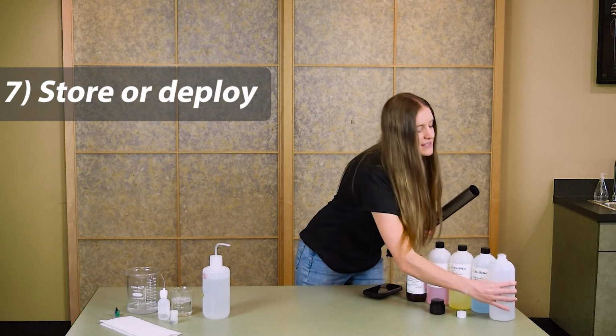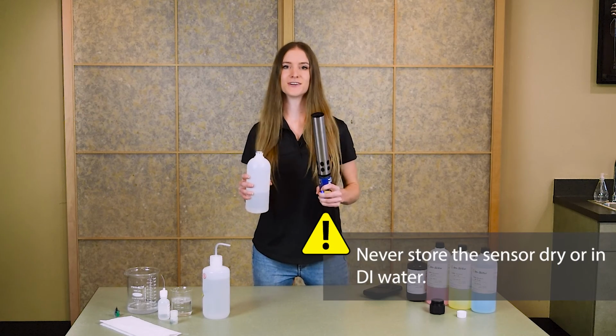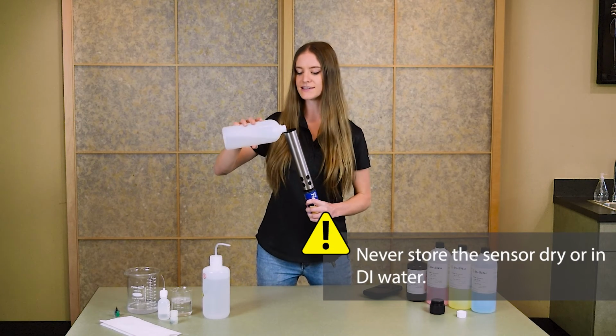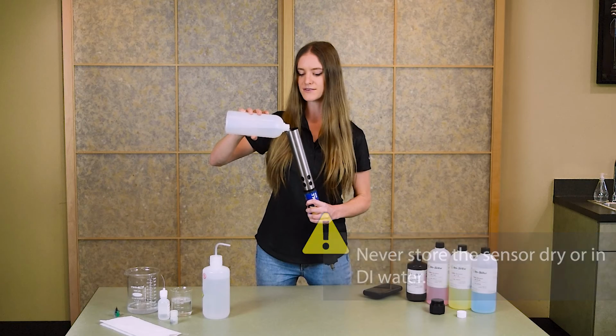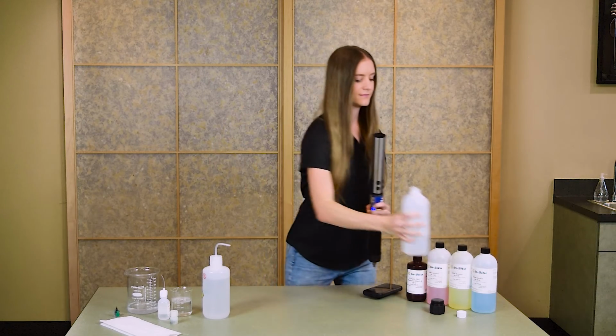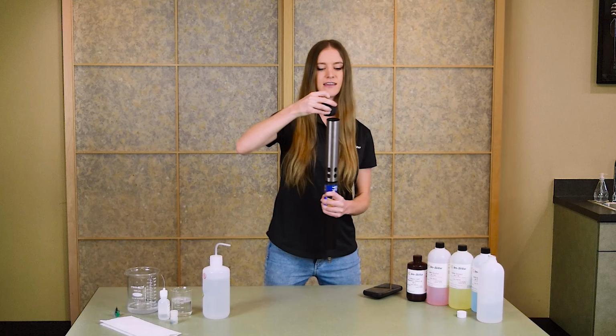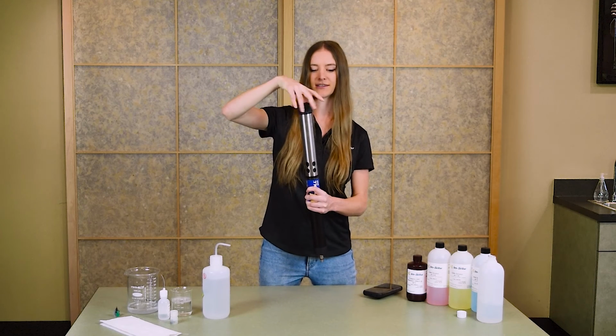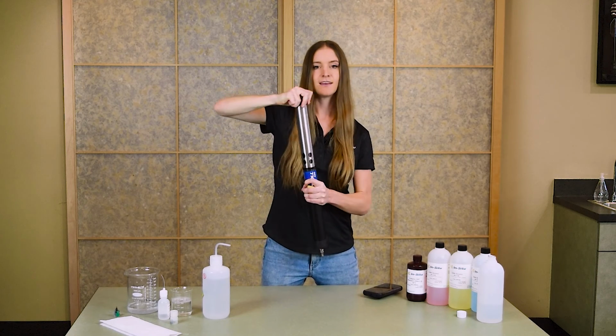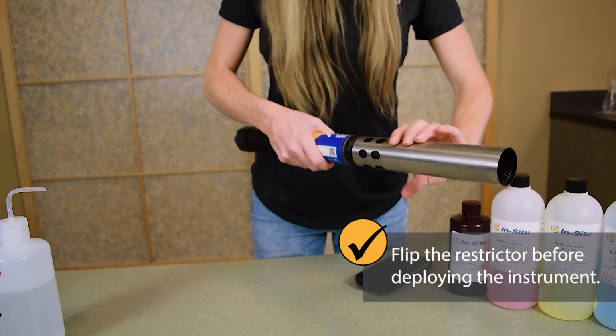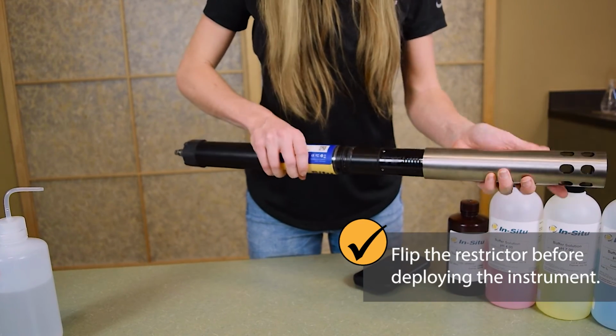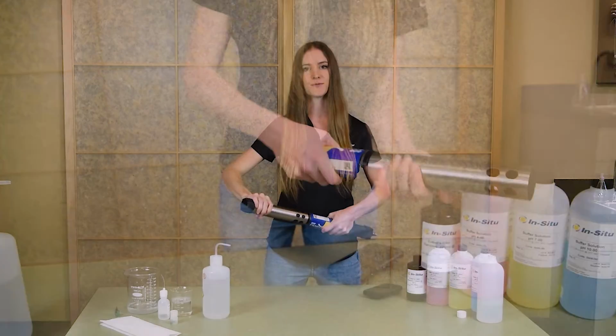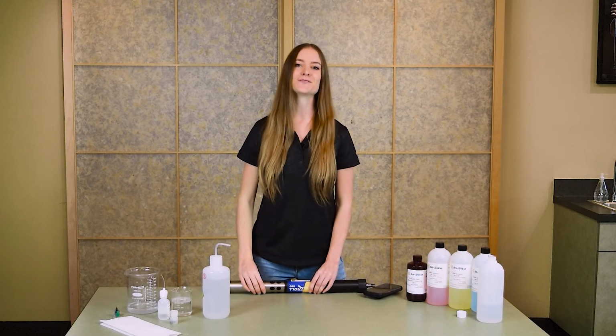If you're going to be storing the sensor for a while, never store it dry or in DI water. Instead, fill the restrictor halfway with storage solution and then reinstall the end cap onto the restrictor. Once you're ready to deploy, don't forget to flip the restrictor into deployment mode with the holes away from the center of the instrument.